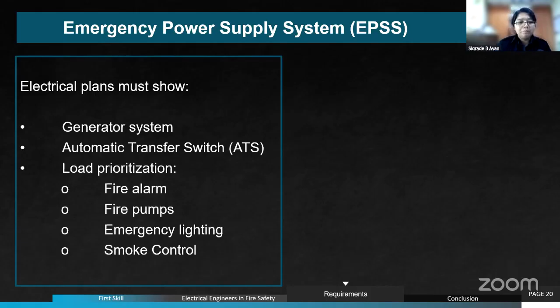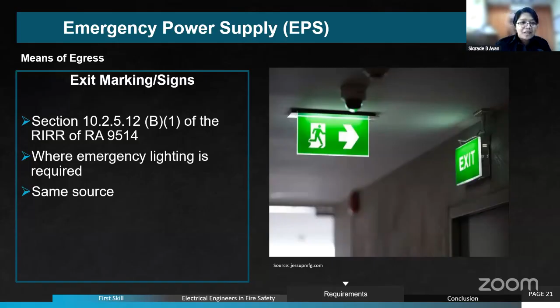While for means of egress, another requirement is the emergency power supply. Exit markings or signs don't need an emergency power supply system, but in accordance with Section 10.2.5.12 para B.1 of the IRR, when emergency lighting is required, we need to provide another source of supply during emergency, which is the emergency power supply. And the condition needed when emergency lighting is required should be the same source as our exit markings. So if EPSS is required for emergency lighting, our exit marking or signs should also be connected with our EPSS.